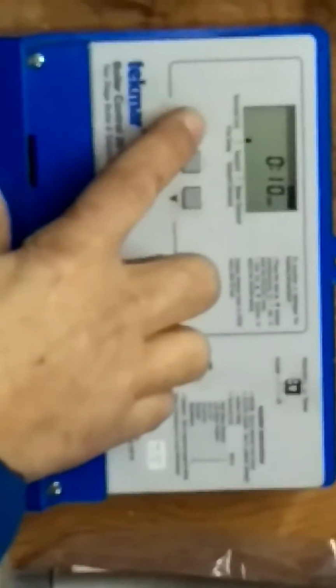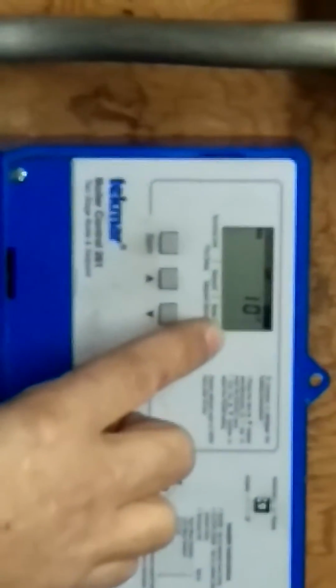The next one is fire delay, which will always be 10 seconds on this type of boiler, 0.10. So 10 seconds, 1/6 of a minute. The differential, which was at 4 or 5 on the heating system, if it's domestic, it'll be at 5. But if it's heating, it'll be at 10, so that it shuts off 10 degrees higher and comes on 10 degrees lower. Warm weather shutdown, WWSD, will be on average at 65, unless it's an old folks home, where it might be a little higher. Warm weather shutdown unoccupied is irrelevant.